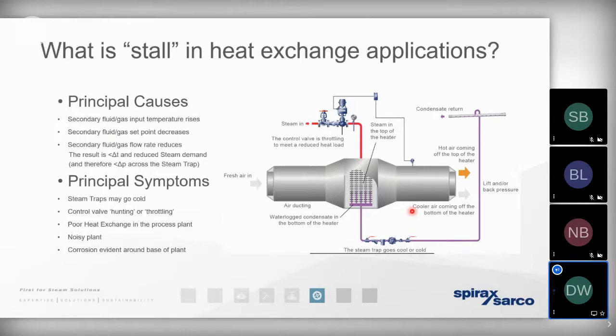Could create a little bit of damage to the steam trap itself, a little bit of back pressure on the steam trap, a little bit of damage to the steam coils. We get the control valve constantly fighting itself. We refer to that as hunting, because it's going to open wider and wider and then close very quickly in a short period of time. But ultimately, we're going to get a failure of the heat exchanger, and we get a very erratic release of heat energy into the process.